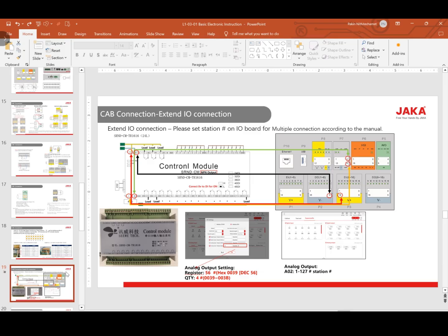When using digital input output, you can see that we only have 16 inputs and 16 outputs. If you want more, you can use the expansion board to connect it. You need to connect using RS485 on A and B, and supply voltage 24 and 0 here, then use your app to extend the controller modules, and you will see the expansion right here.